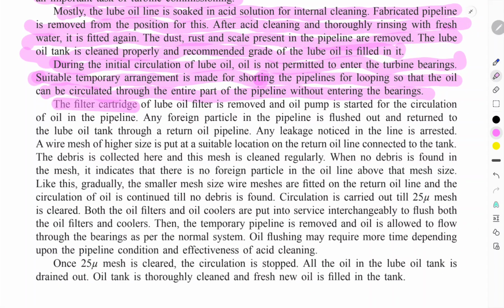The filter cartridge is removed from the lube oil filter and the oil is started circulating through the oil pipeline. Any foreign particles in the pipeline are pushed out and returned to the lube oil tank through the return oil pipeline. Any leakage noticed in the line is arrested, and a wire mesh of higher size is put in a suitable location at the return connection of the tank. The debris is collected here and the mesh is cleaned regularly. When no debris is found in the mesh, it indicates there are no foreign particles above the mesh size. Gradually, smaller mesh sizes are fitted in the return of the oil line.